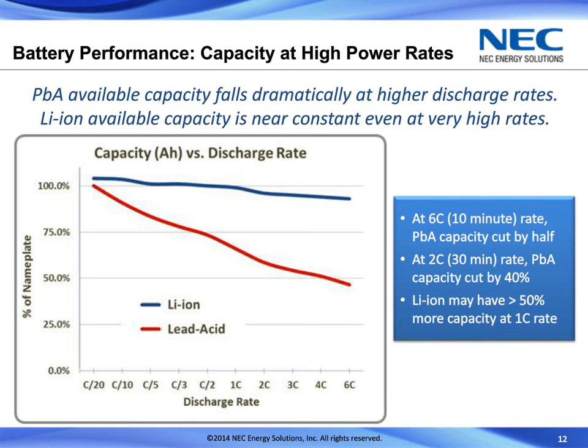So in any application where the battery would be covering a period of time that's less than 20 hours, it would actually be providing less than the rated, what we call nameplate, capacity of the battery. So say you were doing a 2-hour backup scenario, which would be matching up to a C over 2 rate, a 2-hour discharge rate, if you're going to discharge the entire battery in 2 hours. The fact is that a 100 amp hour battery would really only have 75 amp hours of capacity. If you were to do a higher rate, say you wanted to discharge that, the typical, like in a UPS application, maybe in a half hour or maybe even a 6C rate, which would be a 10-minute rate, the actual capacity of that battery would be less than 50% of its rated capacity.